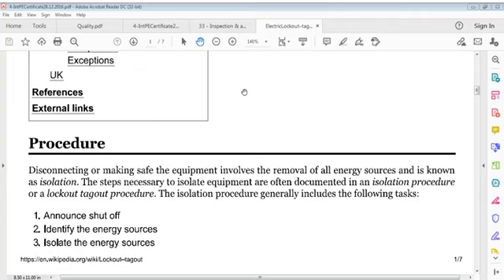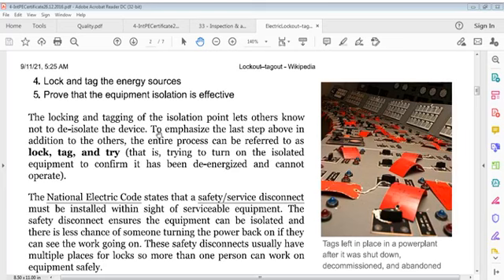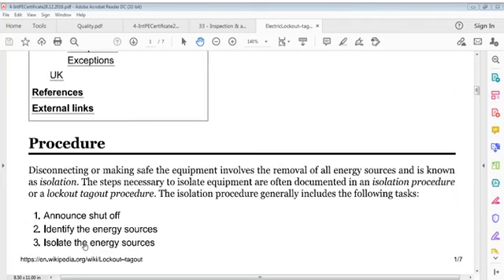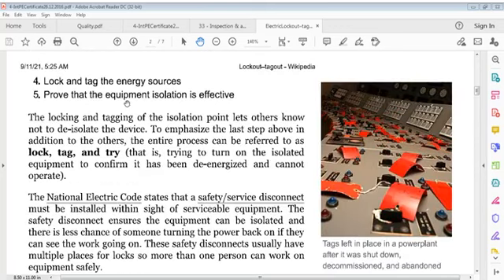Number 1, announce shut off. Announce it: we are going to shut off. Number 2, identify energy sources. Number 3, isolate energy sources. Number 4, lock and tag energy sources. And 5, prove that equipment isolation is effective.